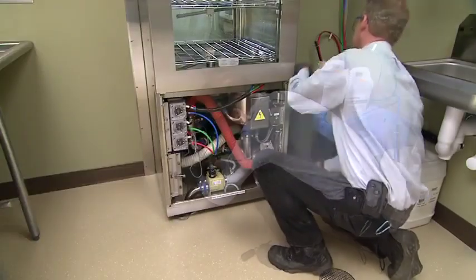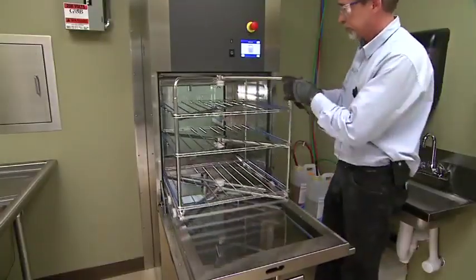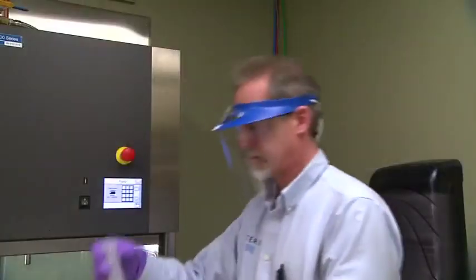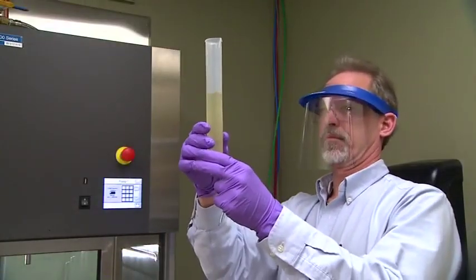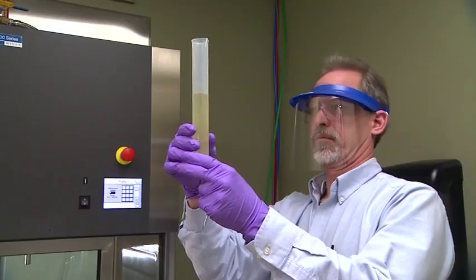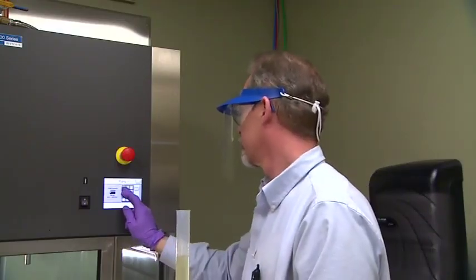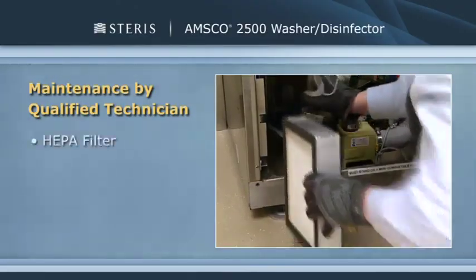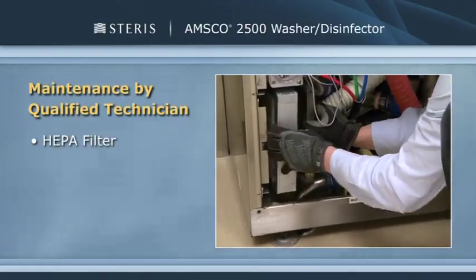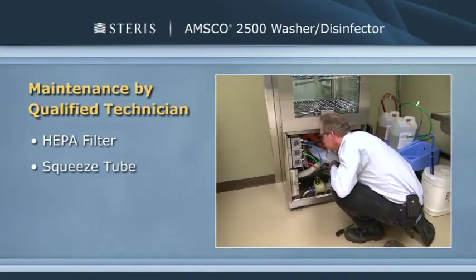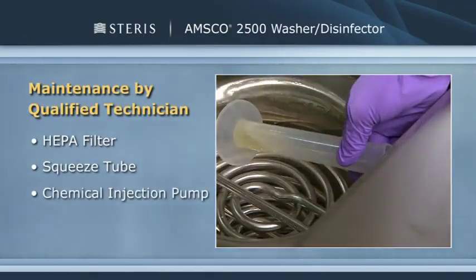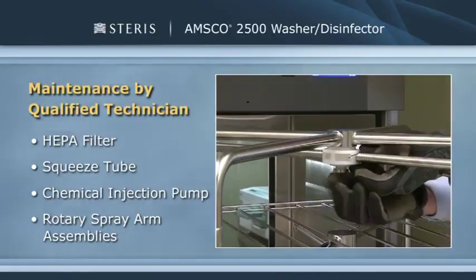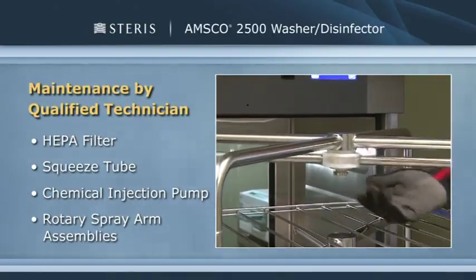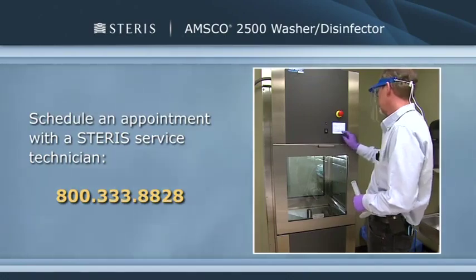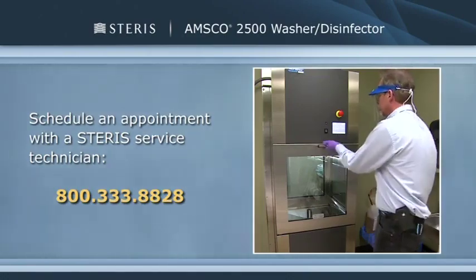In addition to routine maintenance, regularly scheduled preventive maintenance is essential for ensuring peak performance and avoiding unscheduled downtime. Certain preventive maintenance activities must be done by a STERIS service technician or a STERIS-trained service technician in your facility. These activities include HEPA filter verification and replacement, squeeze tube verification, chemical injection pump verification, and inspecting and cleaning the rotary spray arm assemblies.